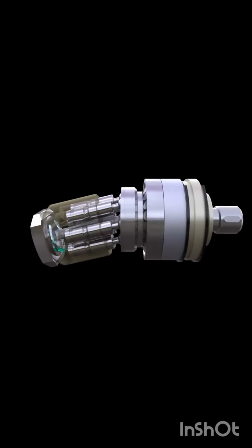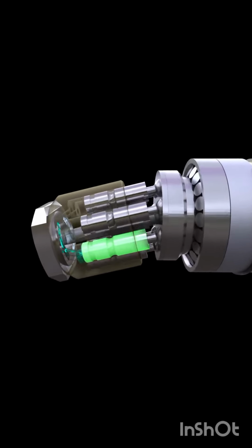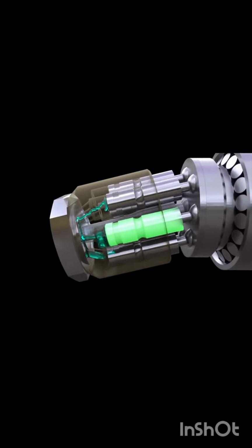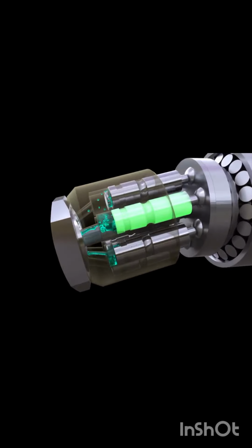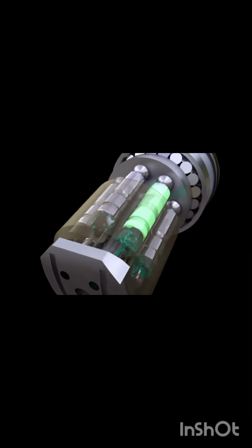The fluid from the tank is supplied to the inlet channel of the pump, from where it is sucked by the pistons. Consider the operating principle of one of the pistons. When moving through the suction area, the piston moves and increases the volume of the working chamber.